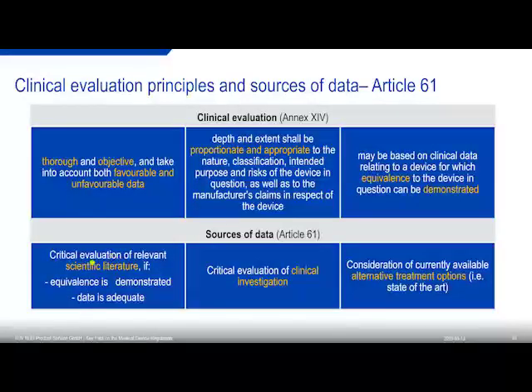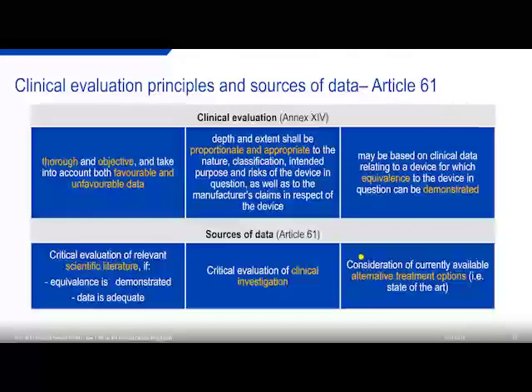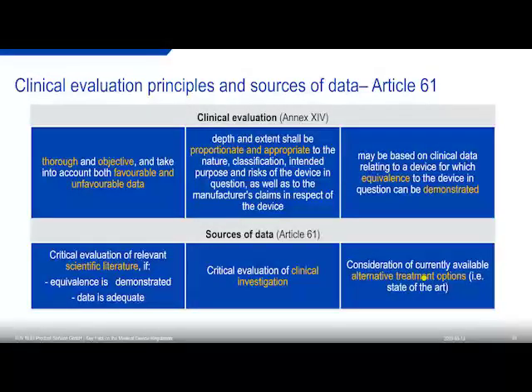So the sources of clinical data are scientific literature still. If you do a proper scientific literature search, which you have to do, you will have one source of clinical data. Then another source of clinical data is your clinical investigations and a critical evaluation of those. Then the consideration of currently available alternative treatment options. So if you have a device that treats something that is also treated by different alternative options, like medicinal options or other devices, then it's something that you have to take into consideration.